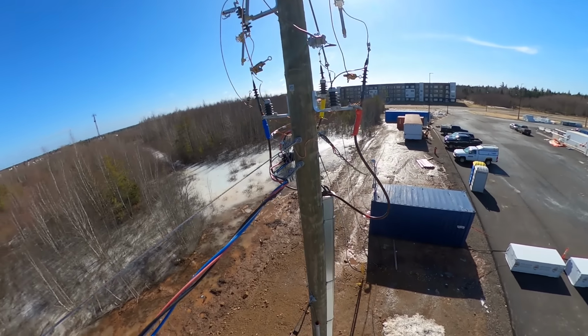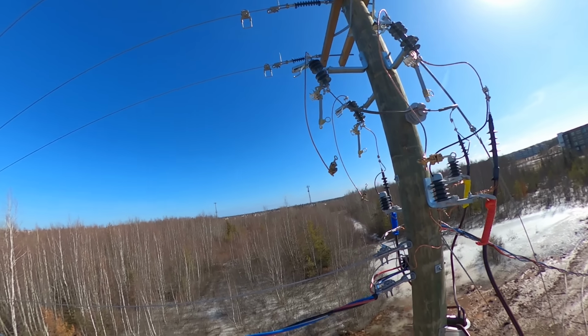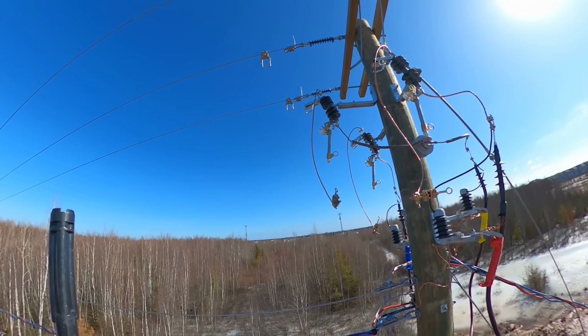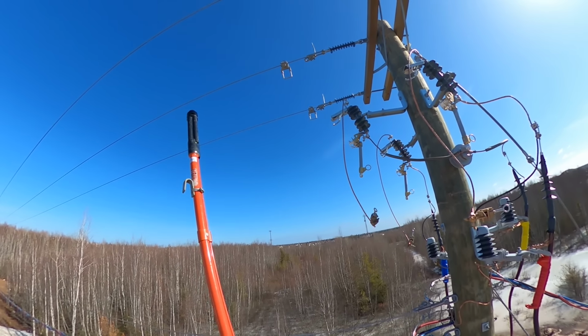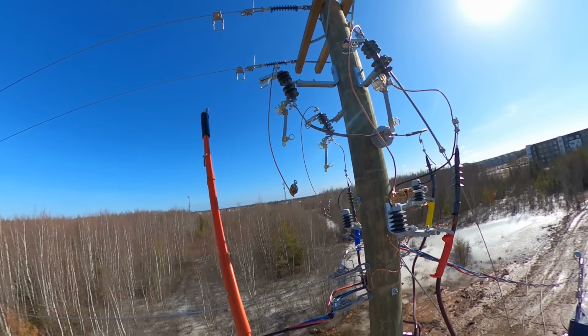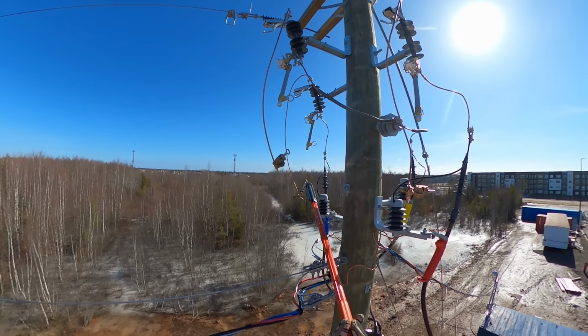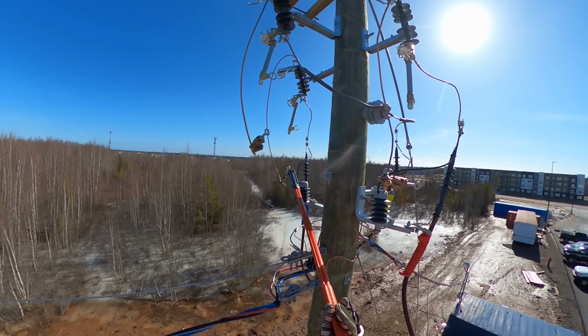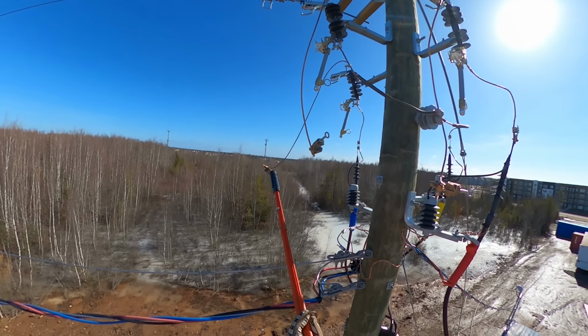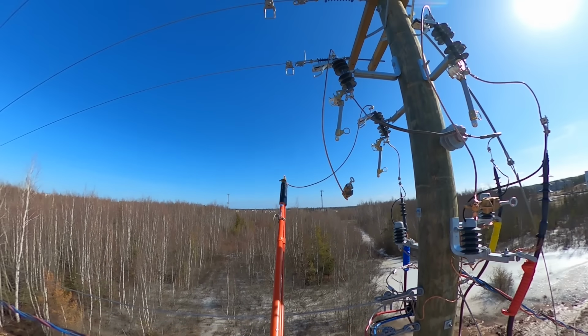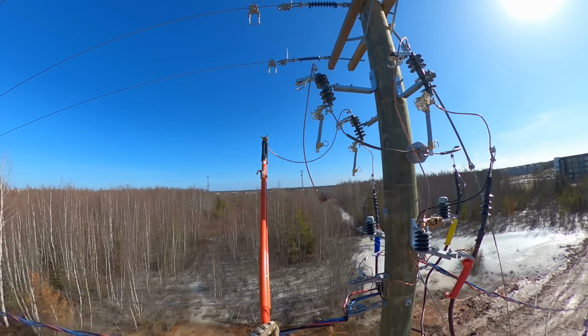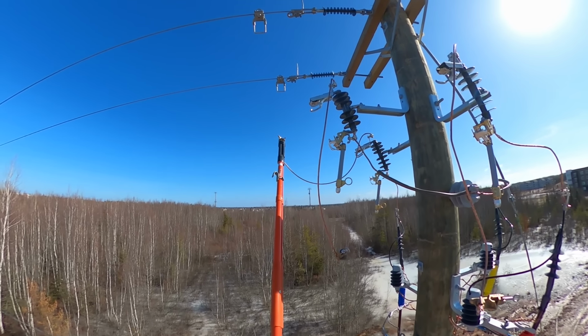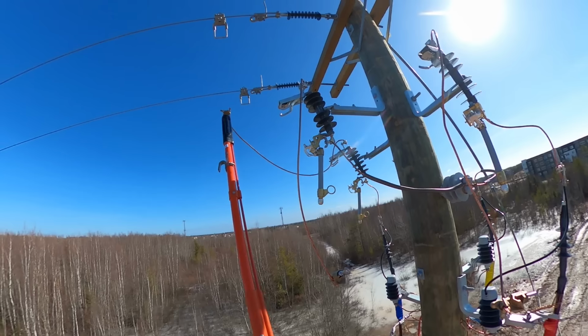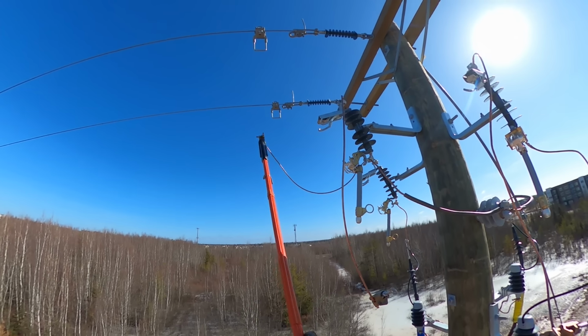Now, as we tap these on, it's important to not work your way in. You don't want to tap the one closest to you and work your way in, because then you're going to be working around live conductors right at your shoulder level. So we're going to start at the far end and tap this one on first. Watching where the lead is, the tails are measured pretty good here, so the lead's not long enough to get into a ground, or the bracket the cutout's on, or another phase or anything like that.